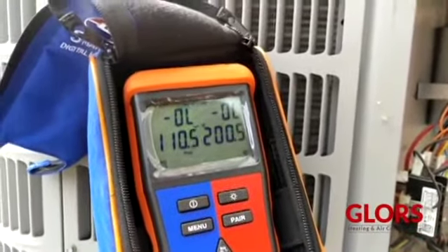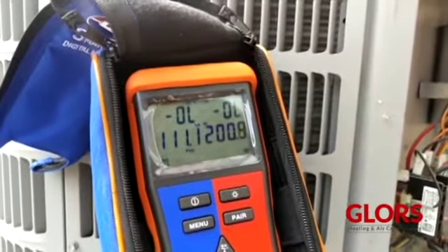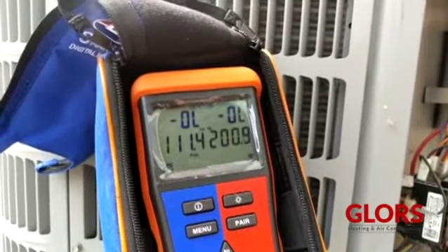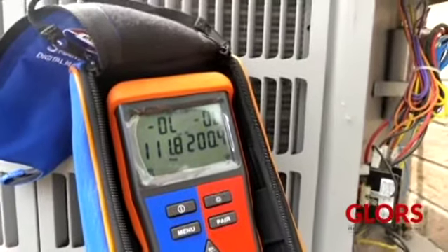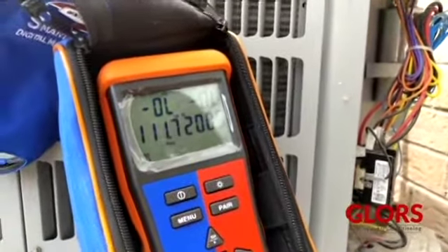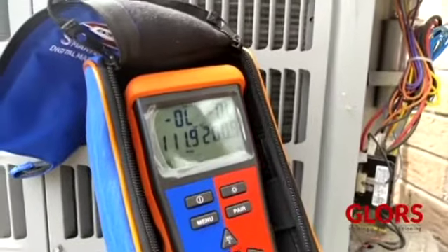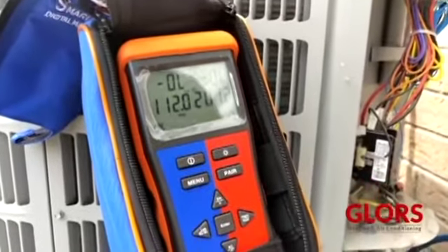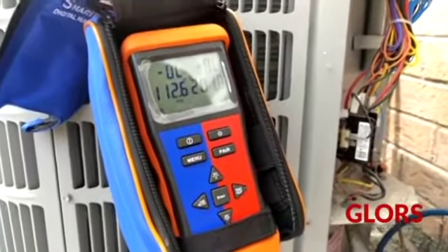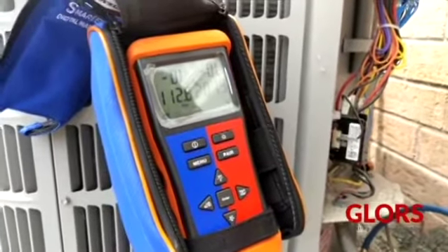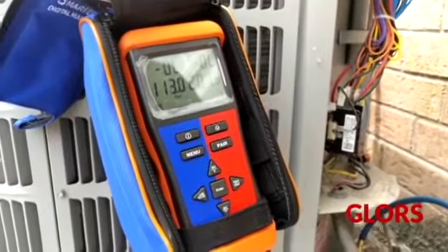That varies with the temperature and weather outside, as well as a bunch of other things that make a difference in the numbers. You need to check superheat and subcooling, which is a little technical for a customer who is not technical, but for me, I checked my readings, and yes, I just need to add a little bit, and I'll explain how and what the consequences are.